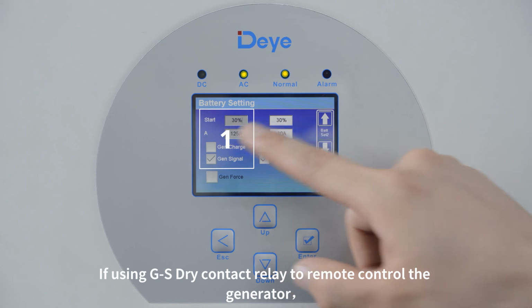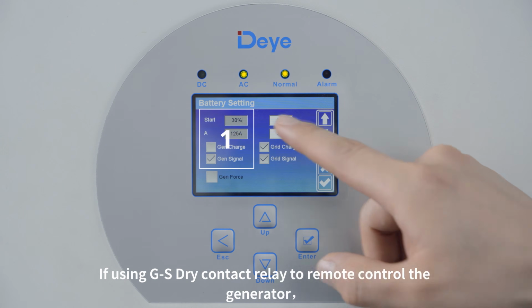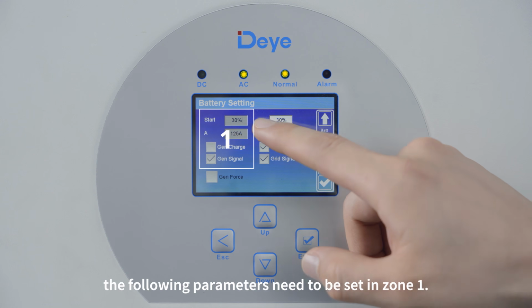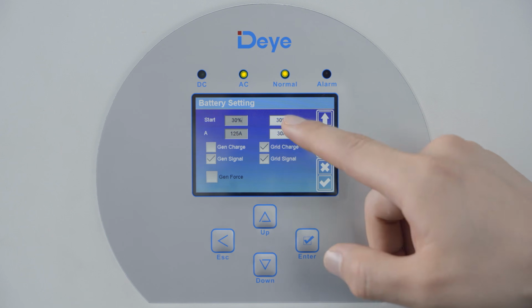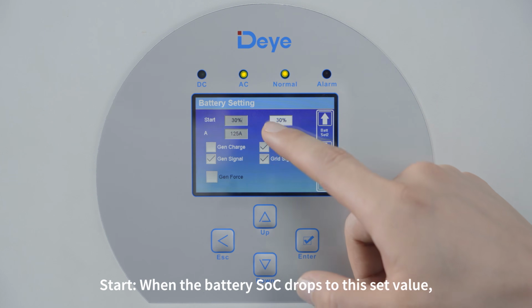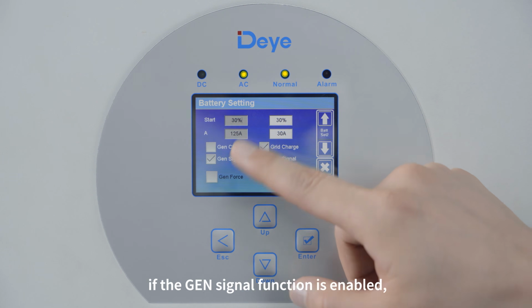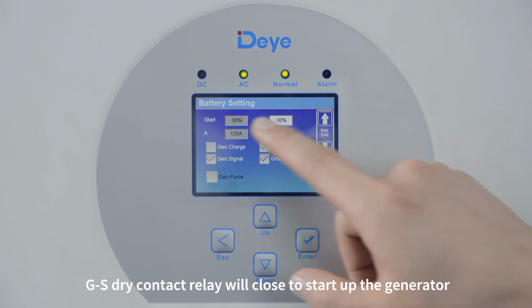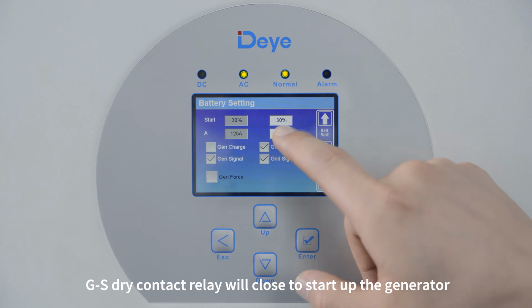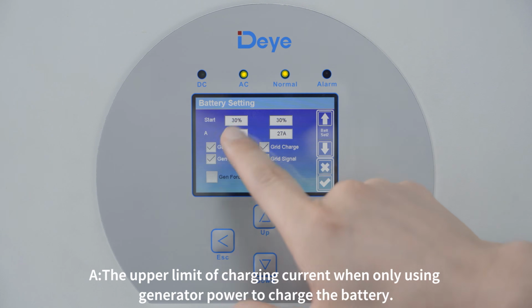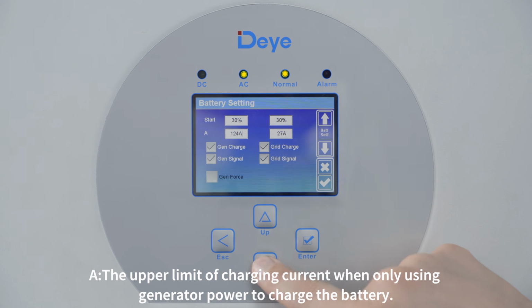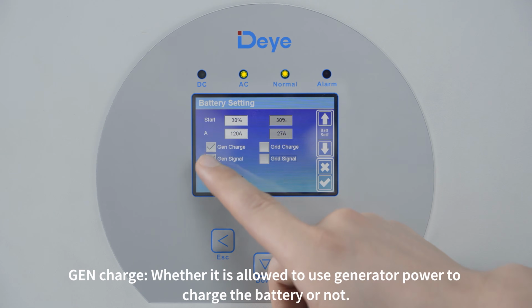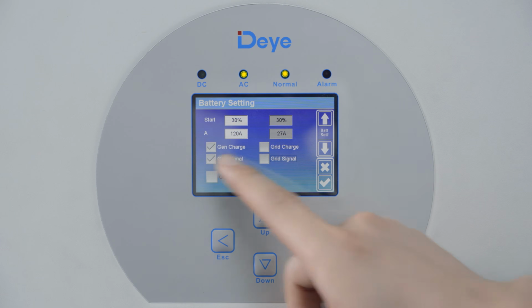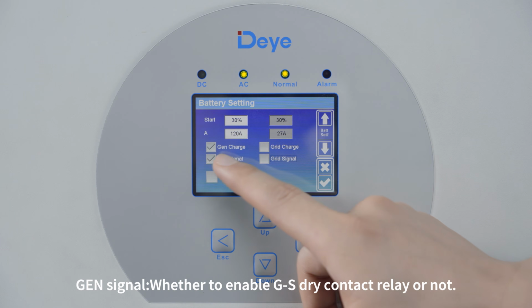If using the GS dry contact relay to remote control the generator, the following parameters need to be set in Zone 1. Start: when the battery SOC drops to this set value, if the GEN signal function is enabled, the GS dry contact relay will close to start up the generator. A: the upper limit of charging current when only using generator power to charge the battery. Gen charge: whether it is allowed to use generator power to charge the battery or not. Gen signals: whether to enable the GS dry contact relay or not.